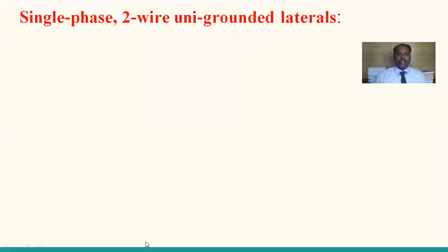In the earlier class, we discussed the single phase two-wire ungrounded laterals. A single phase two-wire ungrounded lateral is converted into a balanced three-phase three-wire lateral. The power losses and the voltage drops are reduced to almost half. If you use a single phase system, the voltage drop and power losses are double compared to transferring the power through the three phase system.